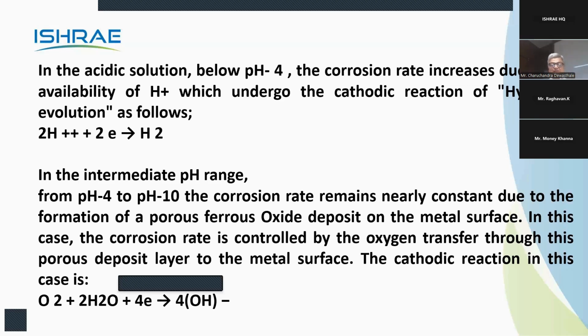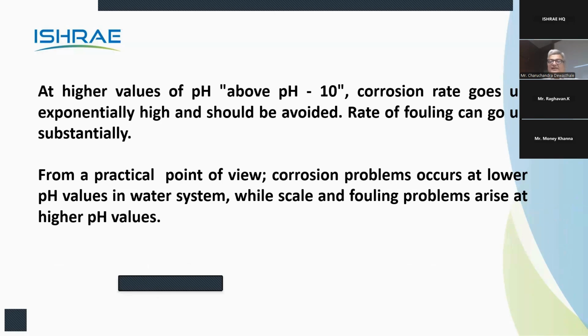So again, I'm repeating that 7 to 9 is the safest range if some film forming agent is applied to the surface. At pH value above 10, the corrosion rate goes exponentially high and should be avoided. Rate of fouling will also go up substantially. What will happen is it will create a congenial atmosphere for algae to grow. Algae is film forming in nature, so algae will travel along into the pipeline and get deposited there. It can deposit onto our condenser tubes also, and that is how the fouling will start. But the trigger to the fouling is pH higher than 10.